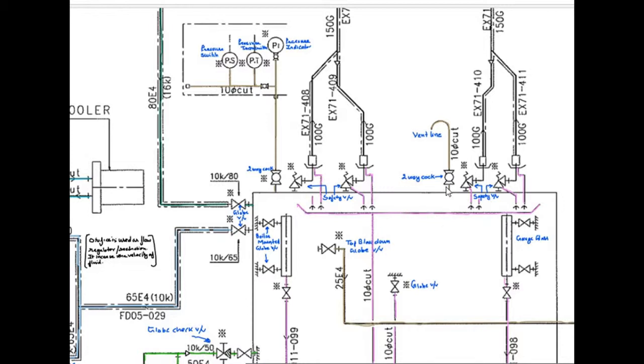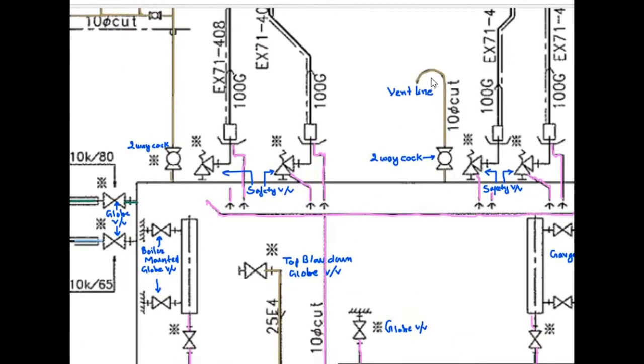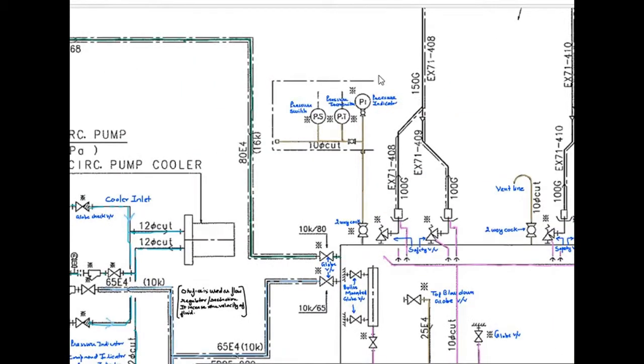For vent, you can see, two-way cock is present. This is a symbol of two-way cock. And vent is present on the boiler. The other line with two-way cock going to pressure indicator, pressure transmitter PT and pressure switch PS.